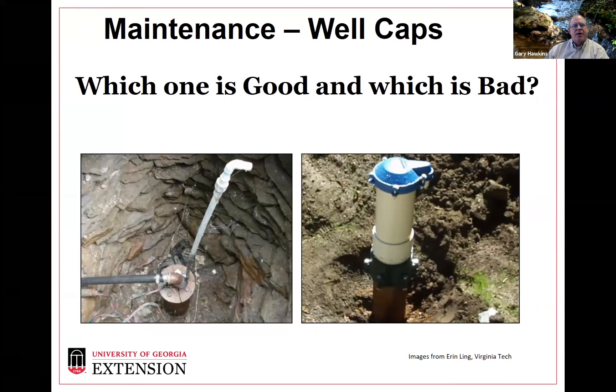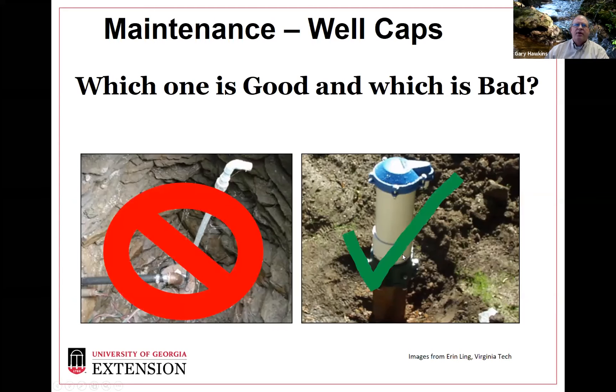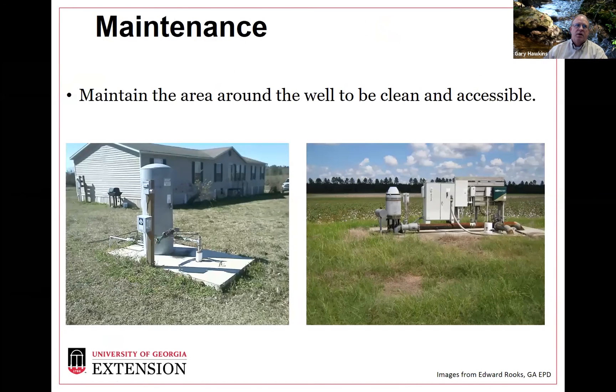When looking at well caps, there's always the good and the bad. The well cap and the well casing itself should stand above the ground surface. The well on the left here is actually below ground surface, with a pipe coming up as a way to access the tap. The one on the right has a good well seal and is above ground level. For maintenance, we definitely want something like the one on the right, not the one on the left, to keep surface water out of the well.